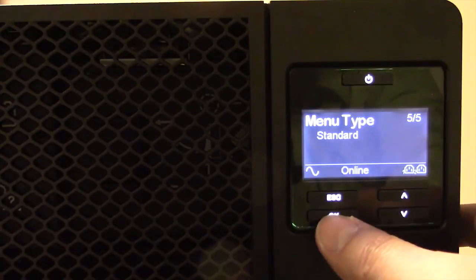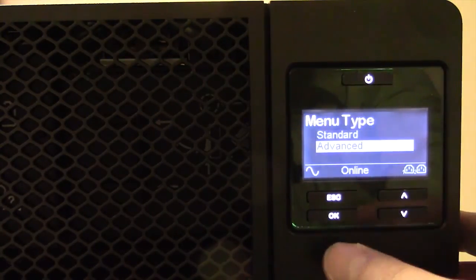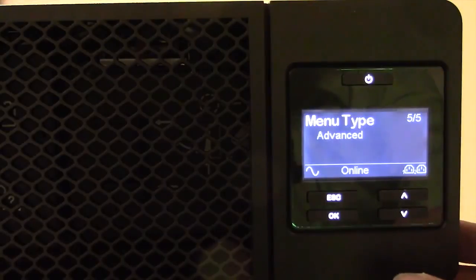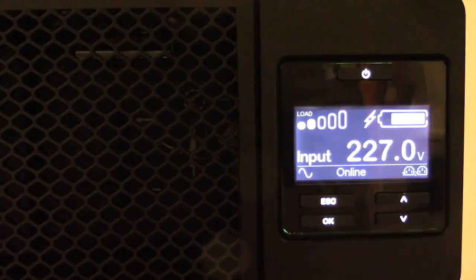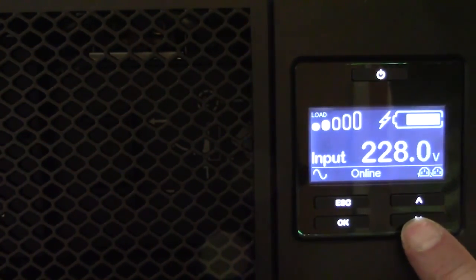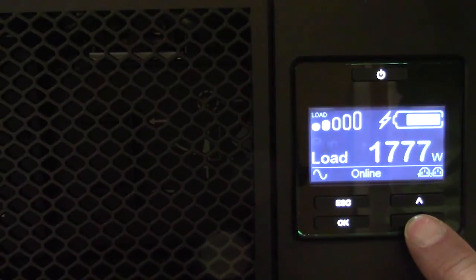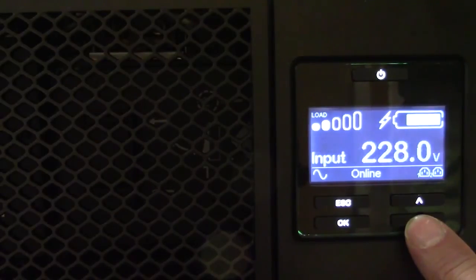If configured to operate in advanced mode, the display will scroll through five different status messages: input voltage, output voltage, output frequency, runtime, and load. The user will be asked to select one of these parameters to display if the LCD is operating in basic mode. Pushing the arrow buttons will cycle the display through the five status messages.